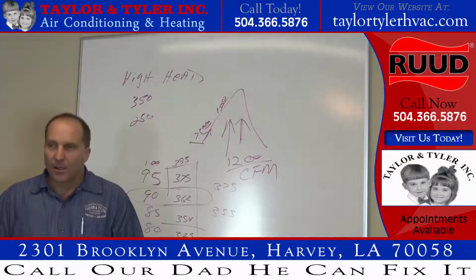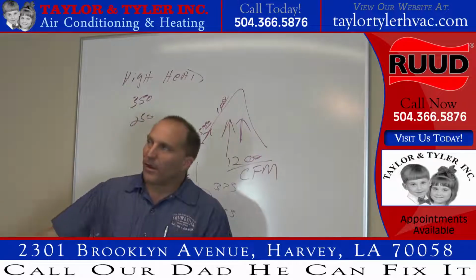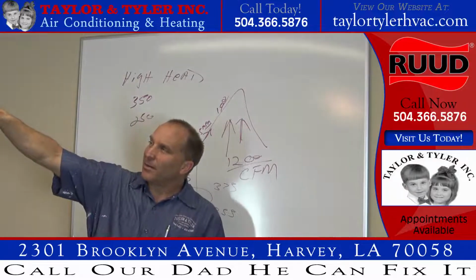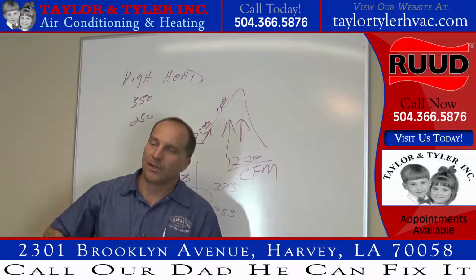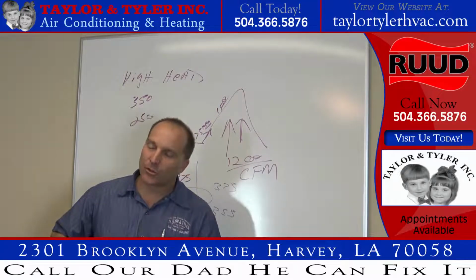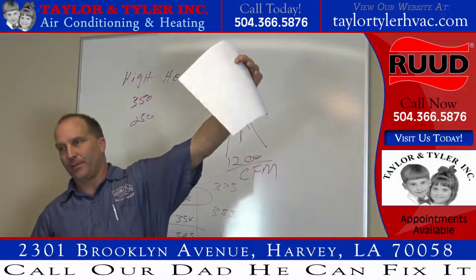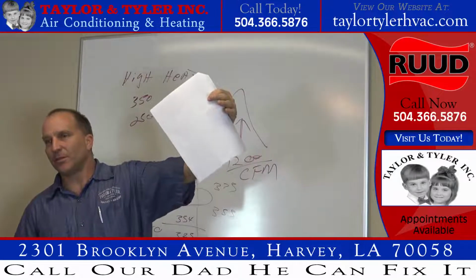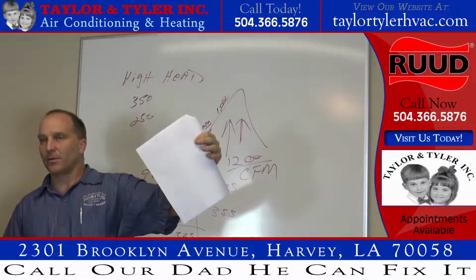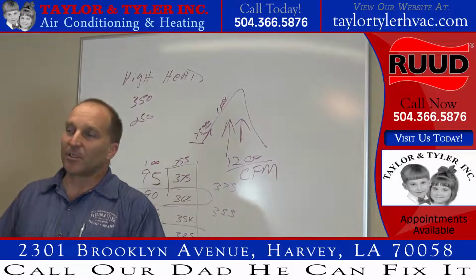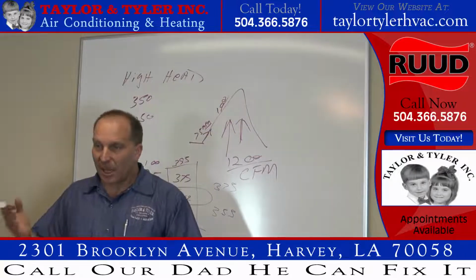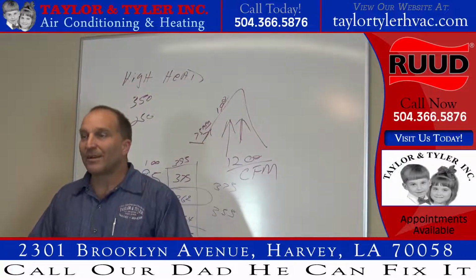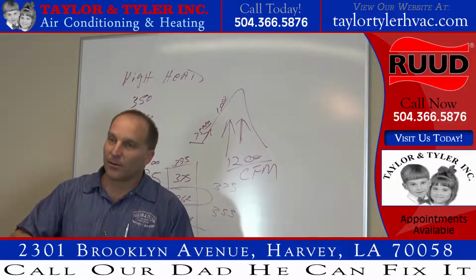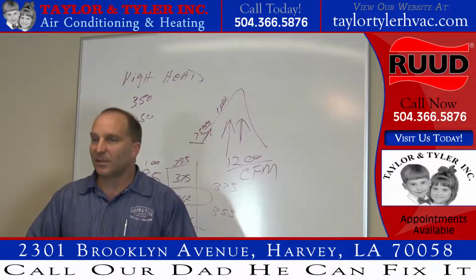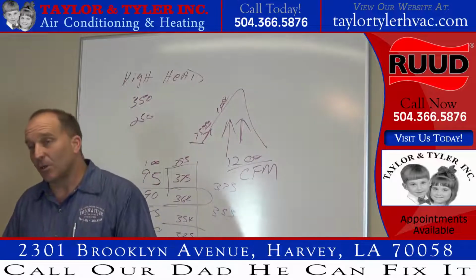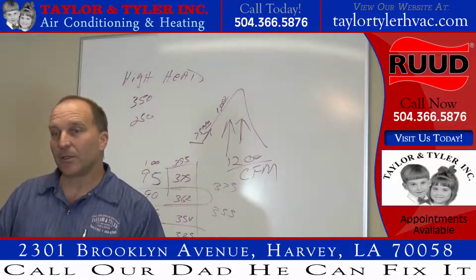Okay? If you have low indoor airflow, that makes the supply temperature coming out of your vent too cold. If it's too cold, that makes your delta T too high. So instead of a 20 degree delta T, it's 28 degrees, 26 degrees, 25 degrees. Increase the blower speed? That's what the slide chart's going to tell you. No. Find out what's causing it to be too low to begin with, which is normally going to be something restricting it. Every once in a while you'll come across one where the blower speed is set wrong.